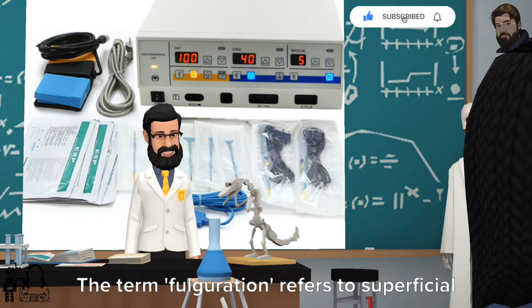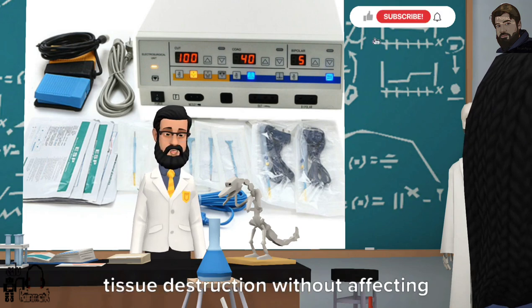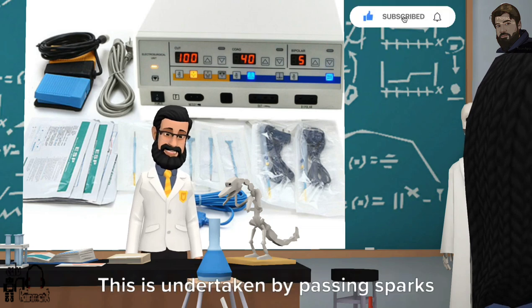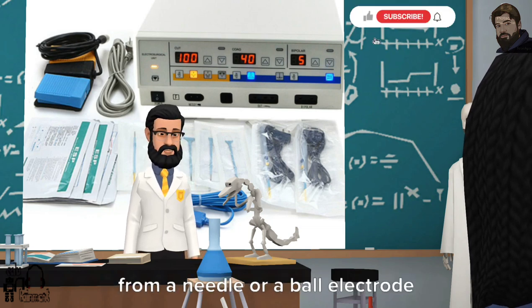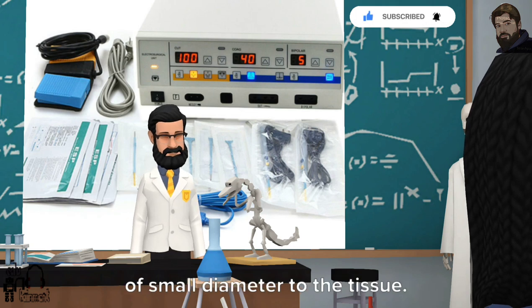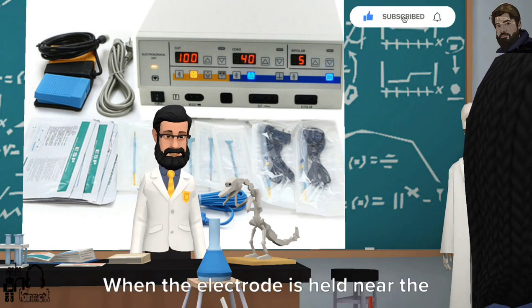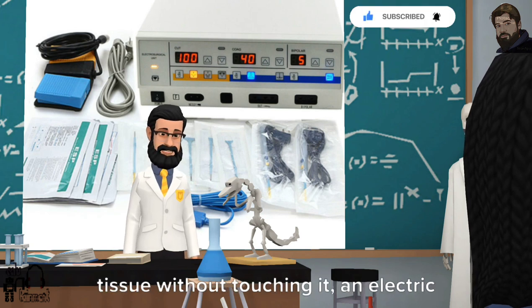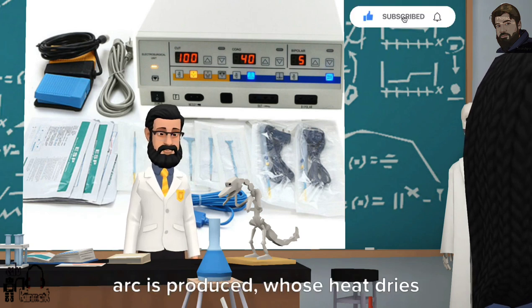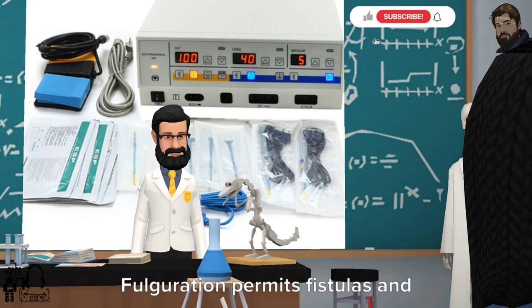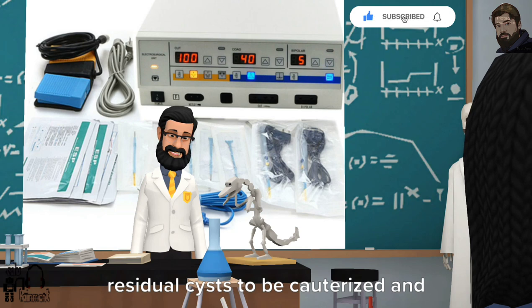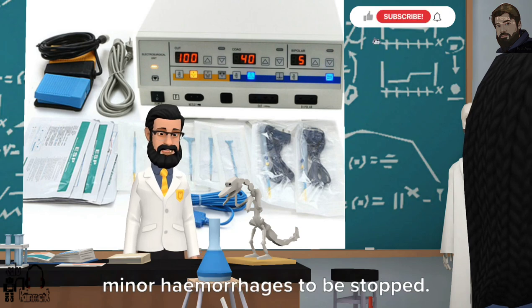What is fulguration? The term fulguration refers to superficial tissue destruction without affecting deep-seated tissues. This is undertaken by passing sparks from a needle or a ball electrode of small diameter to the tissue. When the electrode is held near the tissue without touching it, an electric arc is produced whose heat dries out the tissue. Fulguration permits fistulas and residual cysts to be cauterized and minor hemorrhages to be stopped.